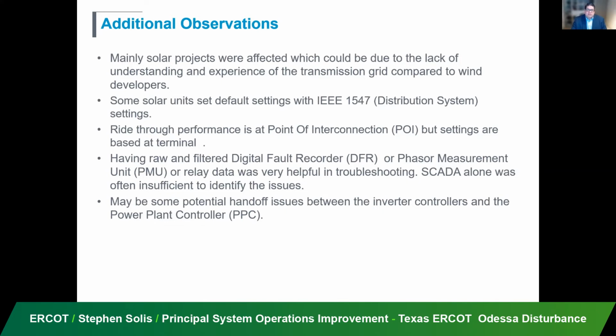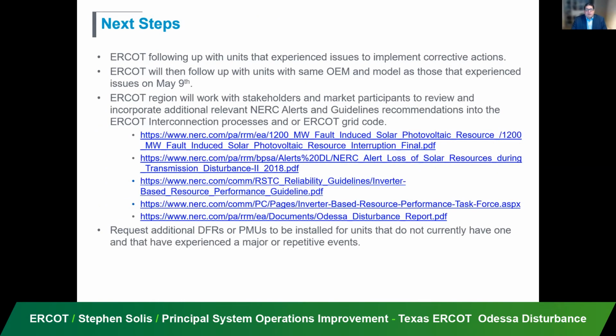It is also interesting to see potentially there's some issues between when an inverter goes into ride-through mode versus when the power plant controller is taking over. And so there's this handoff time period where the inverter is giving control back to the power plant controller, and the system is sitting and doing nothing for a few cycles and then kicks into gear. And when it's kicking back into gear, sometimes it's lost its reference point, and it may actually be adjusting things contrary to what you would expect based on what you see on the point of interconnection system. So that's another thing that we're trying to better understand as we go along.